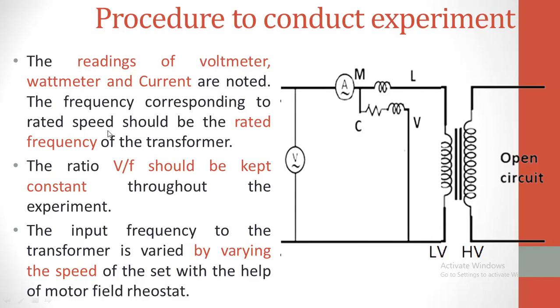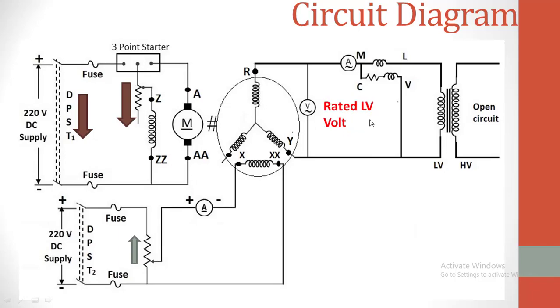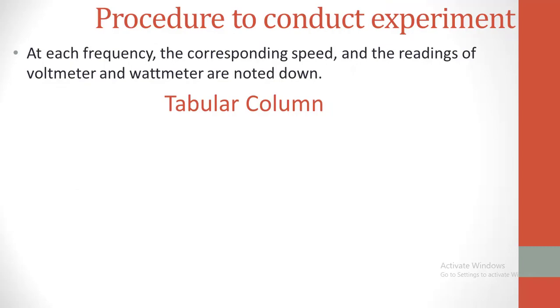The frequency corresponding to rated speed will equal the rated frequency of the transformer. The ratio of V/F is maintained constant throughout the experiment. The input frequency to the transformer is varied by varying the speed of the set with the help of the motor field rheostat. Do the same thing for two or three different speeds. At each frequency, the corresponding speed and the readings of voltmeter and wattmeter should be noted in the tabular column.